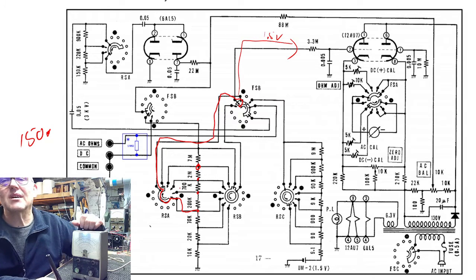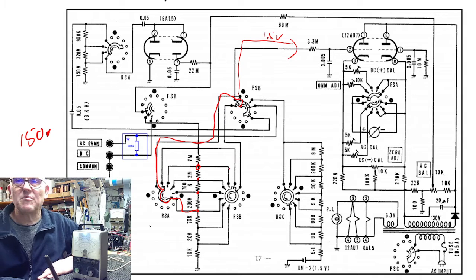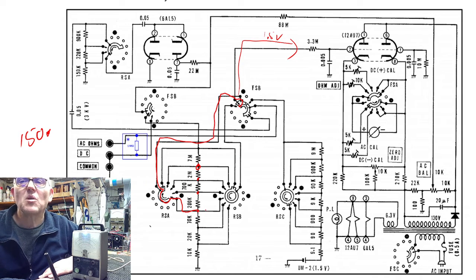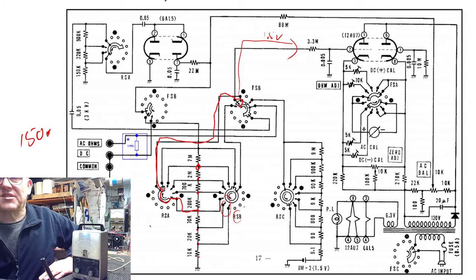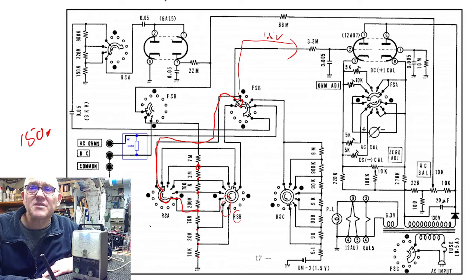Alright. There's a funny thing that happens with this range selector over here, because this is the DC scale. But when we go above 150 volts, you can see down here and down here and down here, these switches only go across to this range selector B for DC. In any case, this range selector output comes to the same place. And then during DC, it's going to pass through the other way, out here, back through there, off it goes, and it works just the same. So range selector A is only used for certain ranges of DC, and range selector B is used for all ranges of DC.